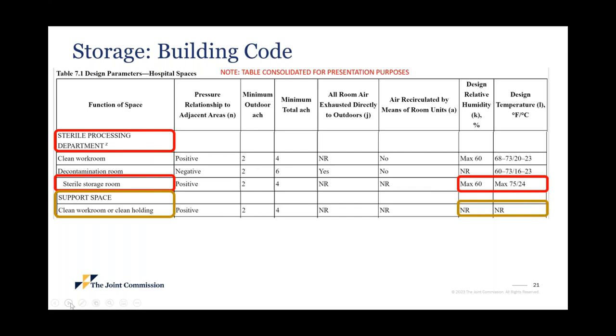What you will notice highlighted in red is sterile processing department, sterile storage room, and then moving to the right, the maximum humidity is 60%, and the design temperature has a maximum of 75 degrees. So the expectation in that sterile supply room would be that you would be able to monitor that those parameters are being met. In that case, you do have to monitor temperature and humidity.